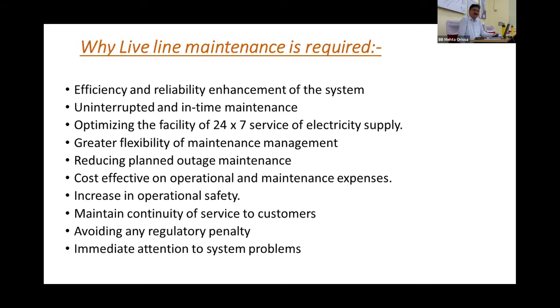It also reduces planned outage maintenance because the outage requirement is addressed within the live line work itself. It also increases operational safety. In my experience with Gujarat, there has never been any accident when the hotline maintenance team has worked, because they are well aware they are working on a live line. Accidents happen when we take an outage, shut down the equipment and start maintenance, but when the person knows he's operating and doing maintenance on a live line charged at 132 to 220 kV etc., there is less chance of any accident. These safety norms are meticulously, very precisely followed, and it gives continuity of supply to the consumer. It avoids any regulatory penalty, as I narrated, and it also ensures immediate attention to system problems.